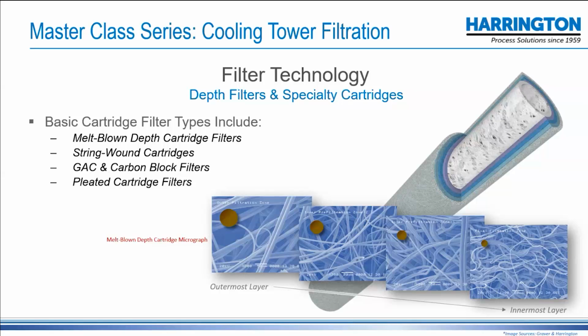Then we have depth filter and specialty cartridges. Depth filter just means it's a melt-blown polypro cartridge, usually. The filter progresses from a coarser fiber to a finer fiber, and that just gives you longer life on the cartridge. You can get very cheap filters that come from Amazon or Asia, but they're mostly a uniform blown. They don't have this feature. It's not much more. In some cases, these are $2 or $3 filters.